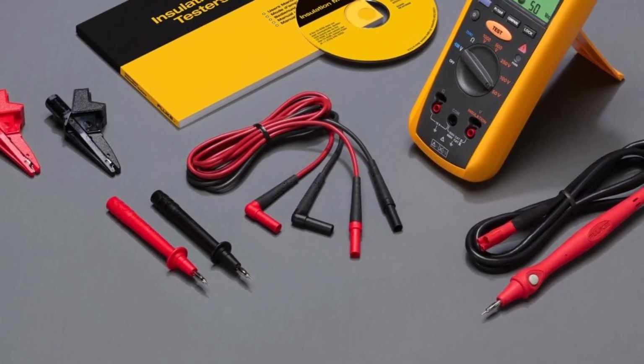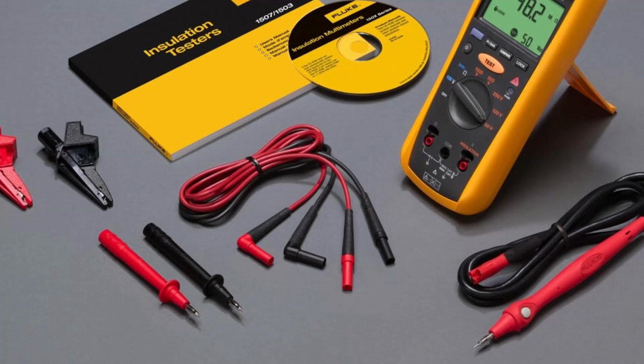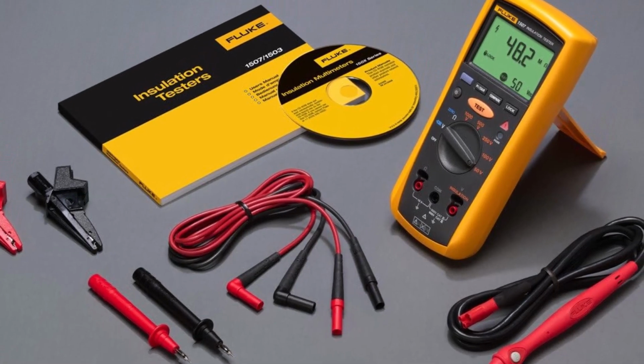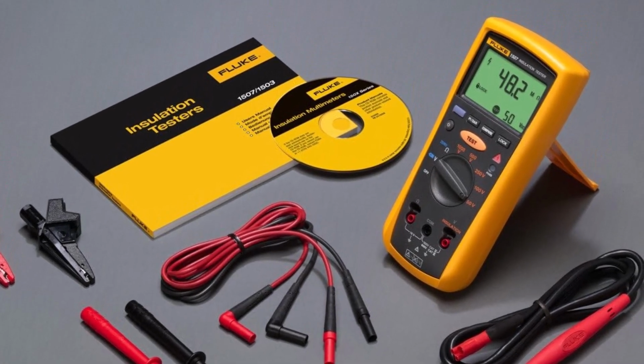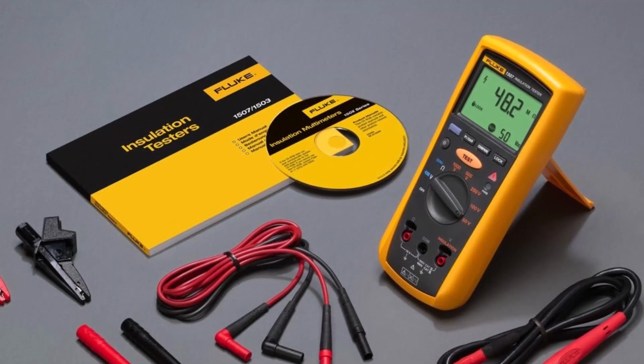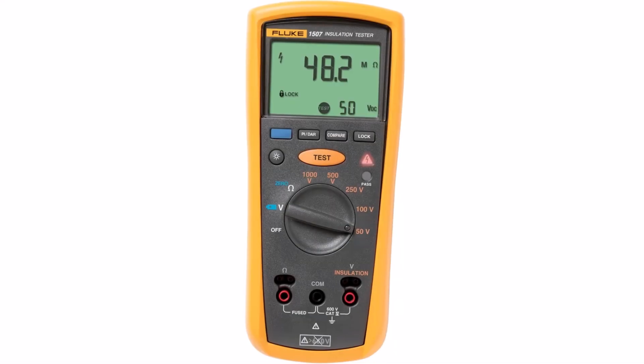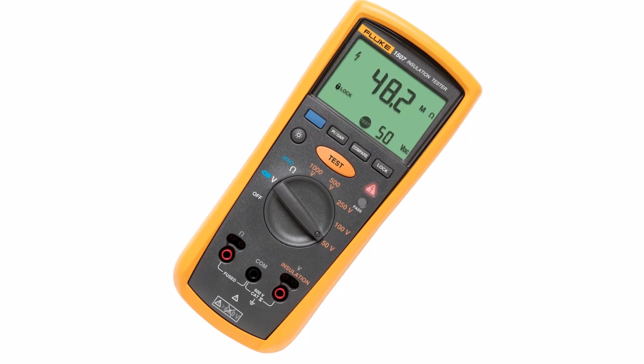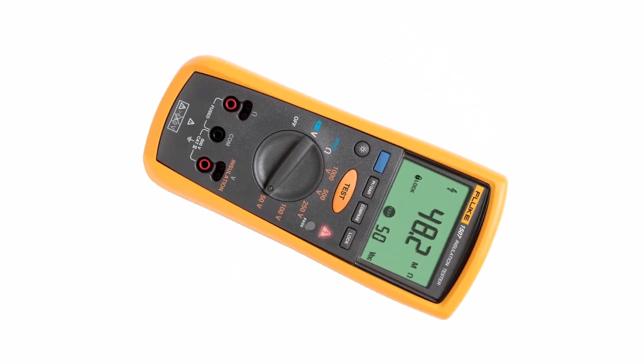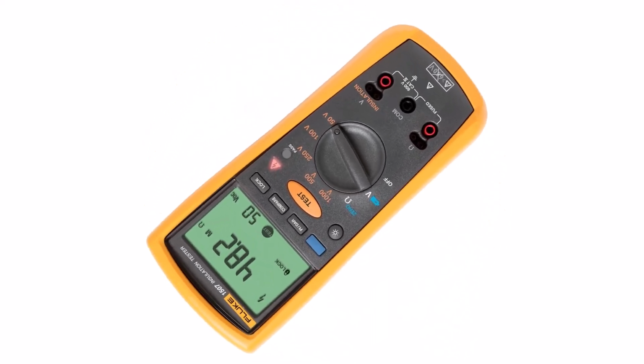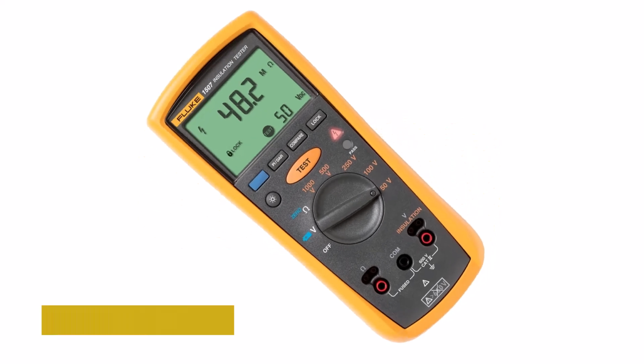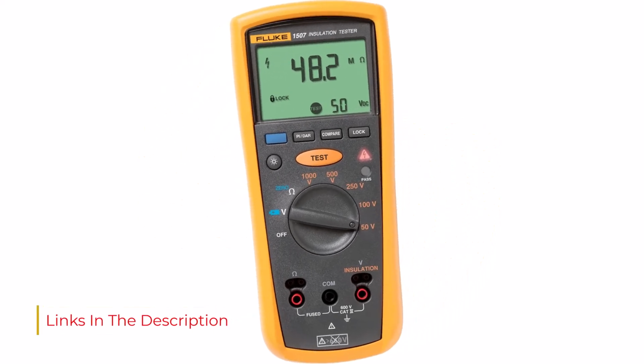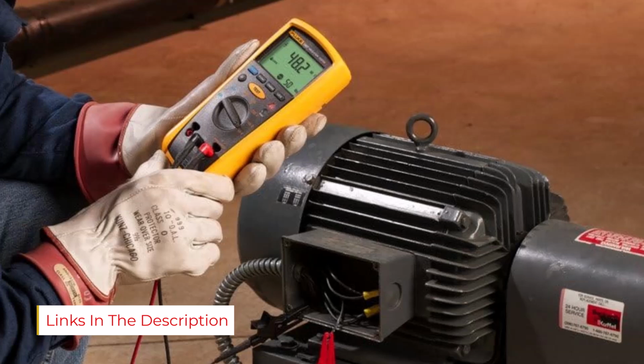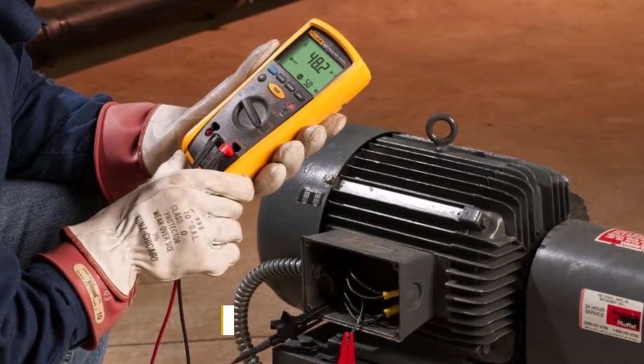As the name suggests, this device is designed for high-capacity applications and its resistance testing range is from 0.01 megohms all the way up to 10 gigohms. And since the device is still quite compact, it would be an ideal choice for testing heavy machinery on site. To make the testing process even easier for you, you will also find an additional remote test probe included within the package that allows you to test circuits from hard-to-reach areas.